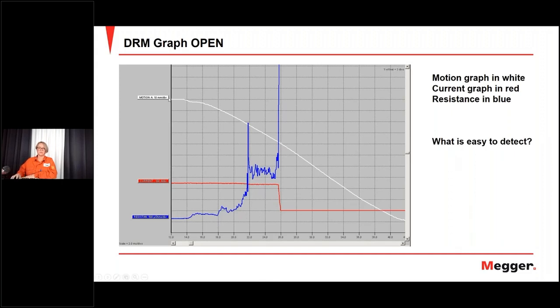You have a motion, it's an open operation, so it starts here, and it goes from closed position to open position, and static down here. And you have a resistance, which will increase even more, making like a stack, and then it goes to total maximum of a measurement channel, actually, because the channel has a maximum here. But of course, this is max resistance. This is open, right? And here you have a current, more or less static, and then it's dropping to zero.